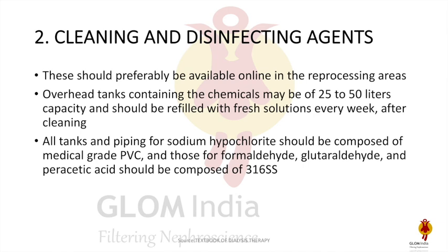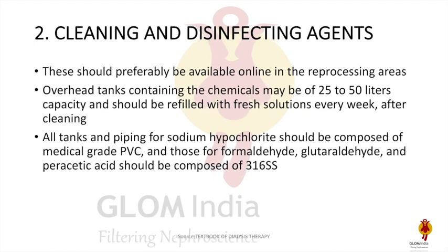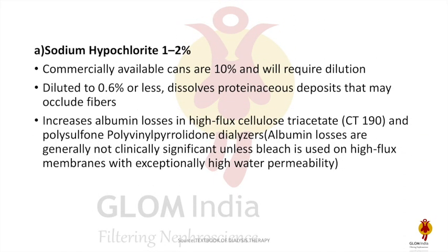Ideally, the disinfecting agent should be available online with 25 to 50 liter capacity tanks, refilled with fresh solution every week after cleaning. All tanks and piping for sodium hypochlorite should be composed of medical-grade PVC, while those for formaldehyde, glutaraldehyde, and peracetic acid should be composed of 316 stainless steel.